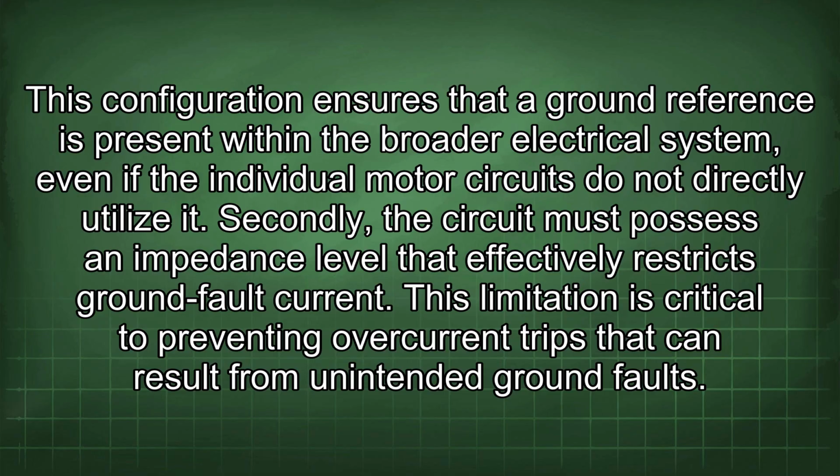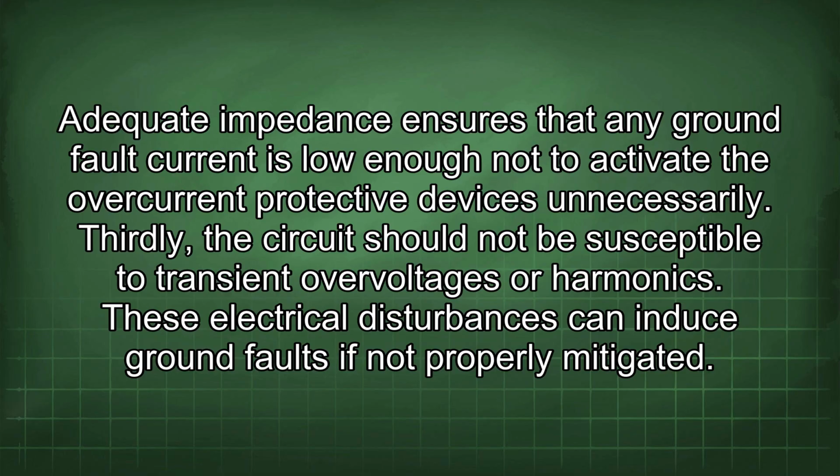Secondly, the circuit must possess an impedance level that effectively restricts ground fault current. This limitation is critical to preventing overcurrent trips that can result from unintended ground faults. Adequate impedance ensures that any ground fault current is low enough not to activate the overcurrent protective devices unnecessarily.